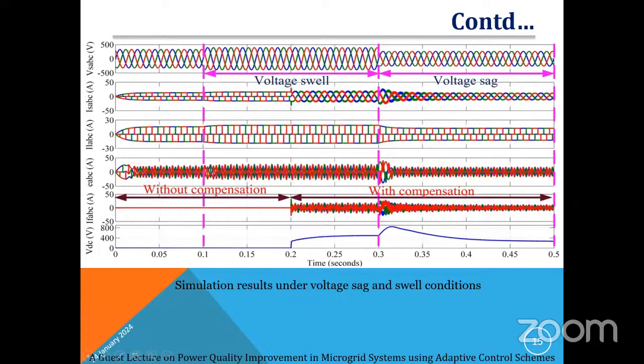So what is the compensating current here? If your system has harmonics, several types of harmonics, then by using this controller, the controller can develop anti-harmonic current, which is opposite of the harmonics, exactly 180 degrees opposite of the harmonics. After injecting this compensating current, the actual harmonic currents plus this current will cancel each other out. Then your currents are maintained as sinusoidal.